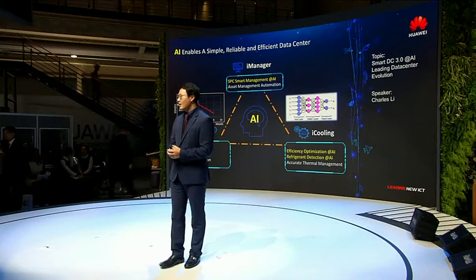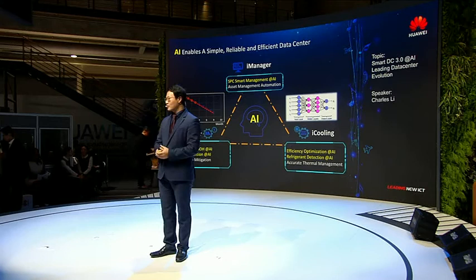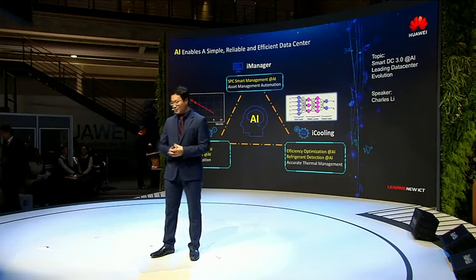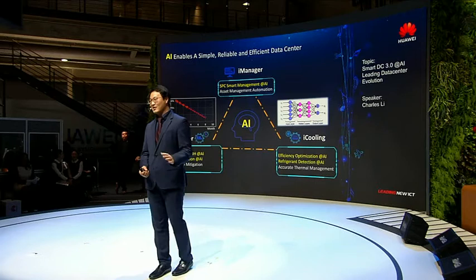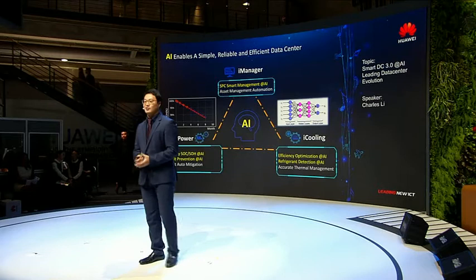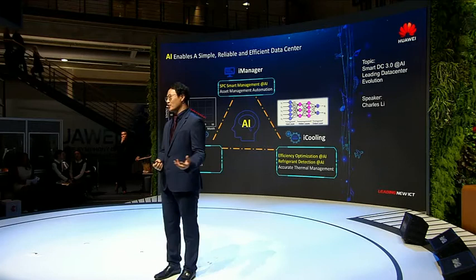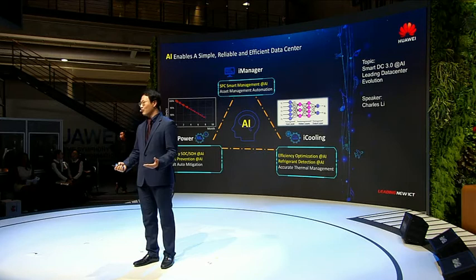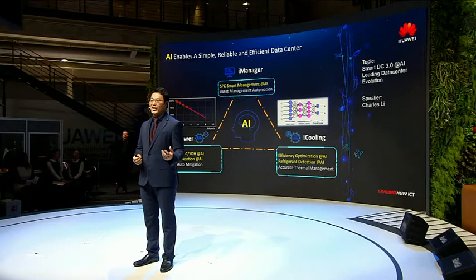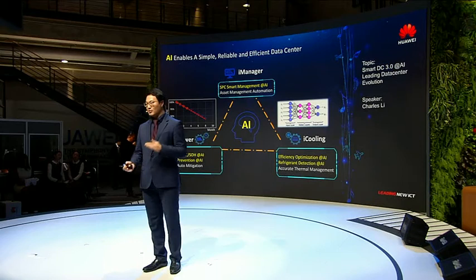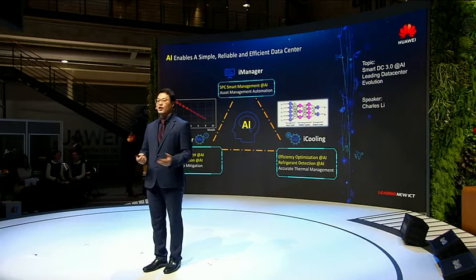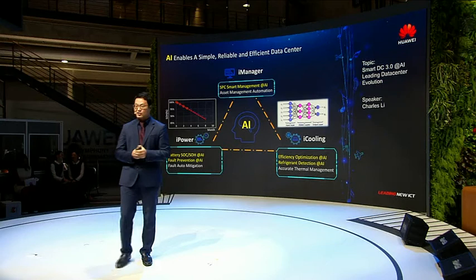We also have refrigerant detection. There are real cases where, after a data center is installed, the refrigerant charge is insufficient — sometimes less than 50%. You don't know the refrigerant is low, and after running for half a year or one year, the cooling system goes down causing a major fault. With our solution, we collect many factors about the refrigerant and monitor its status in real time, so if any refrigerant is missing or conditions are not good, the management system will alert you.